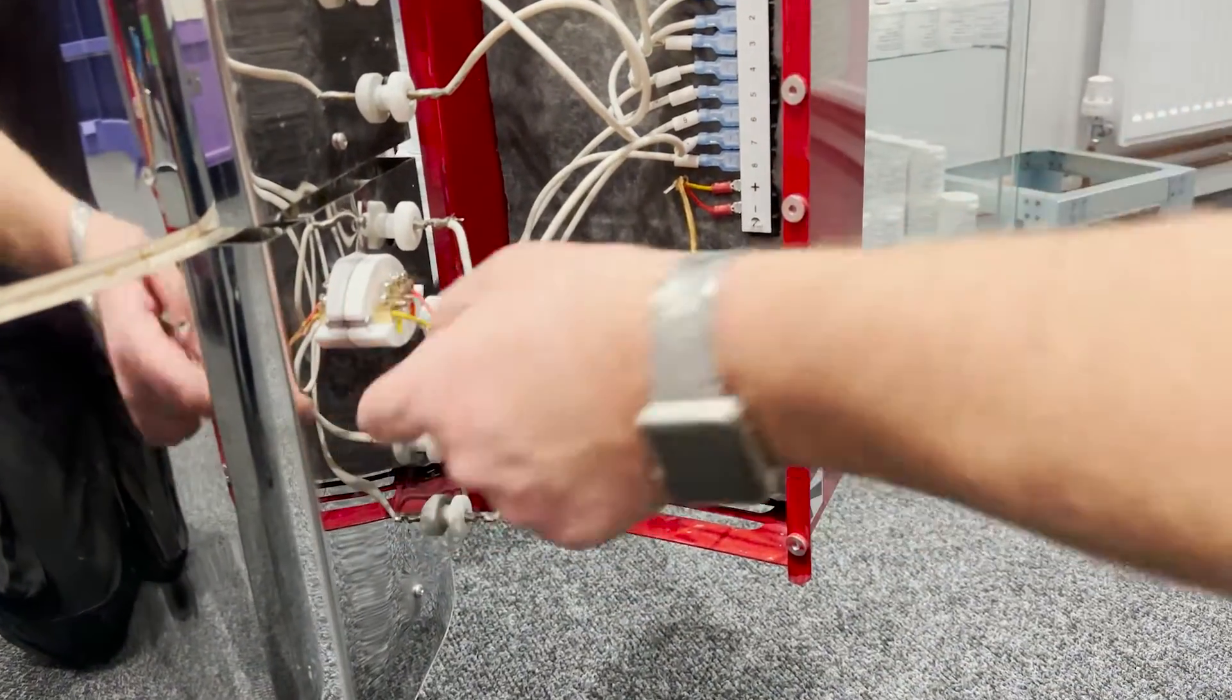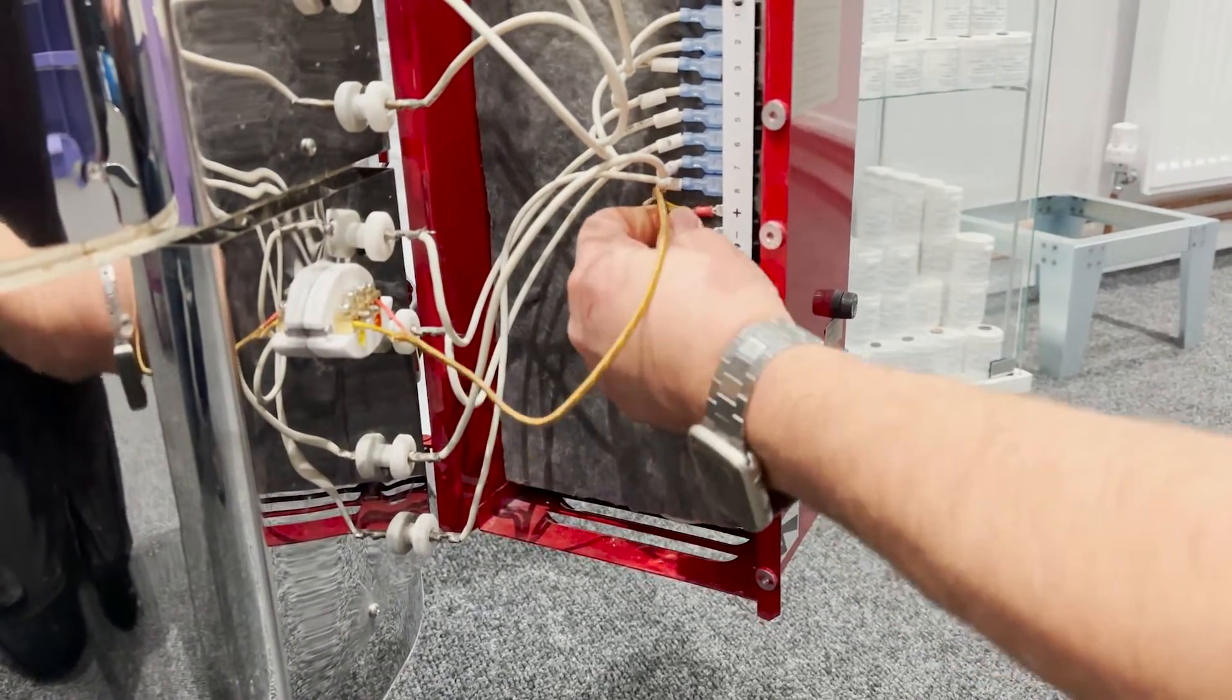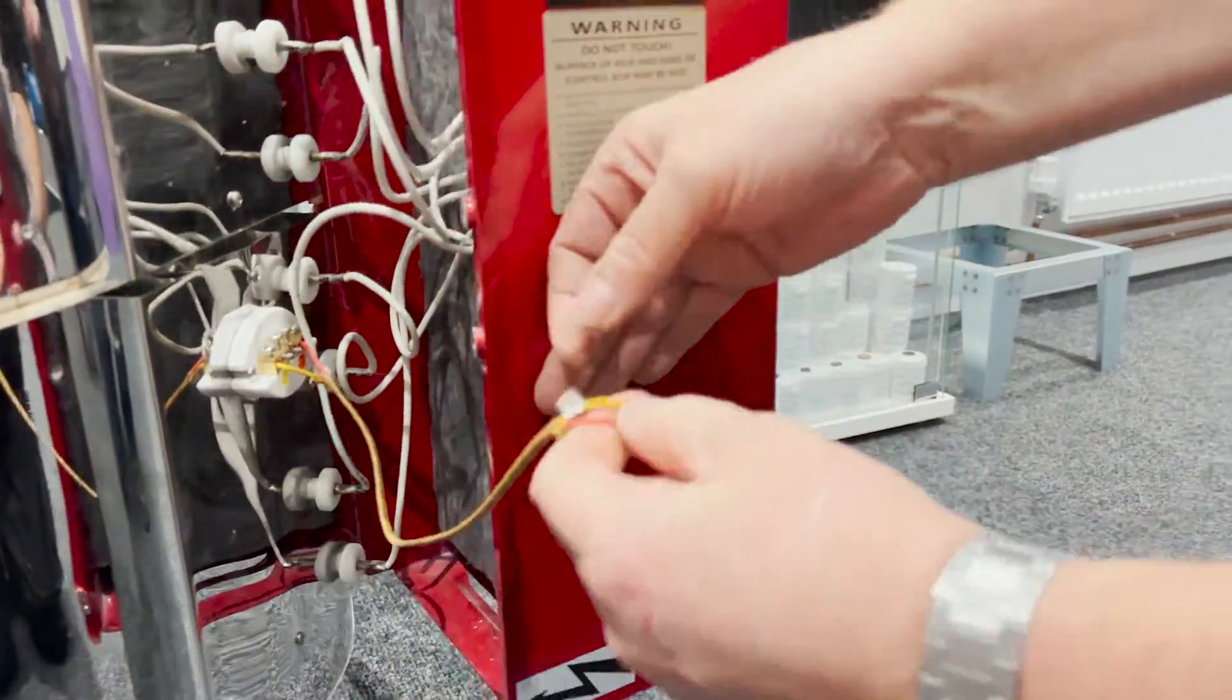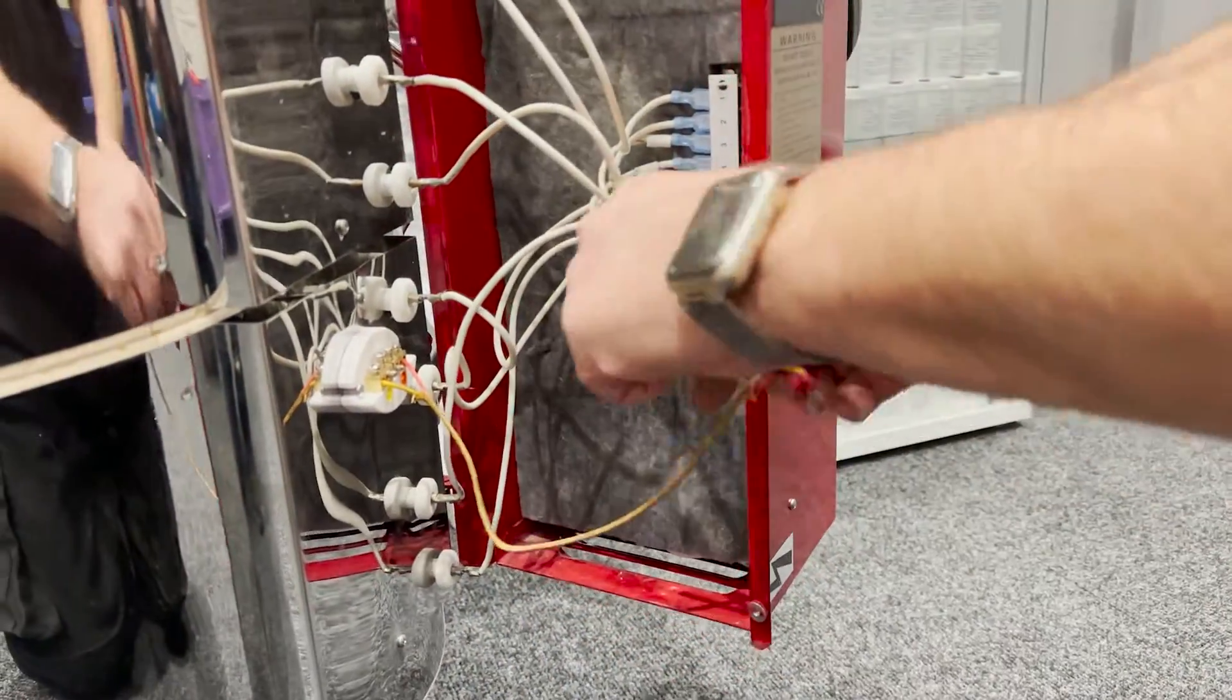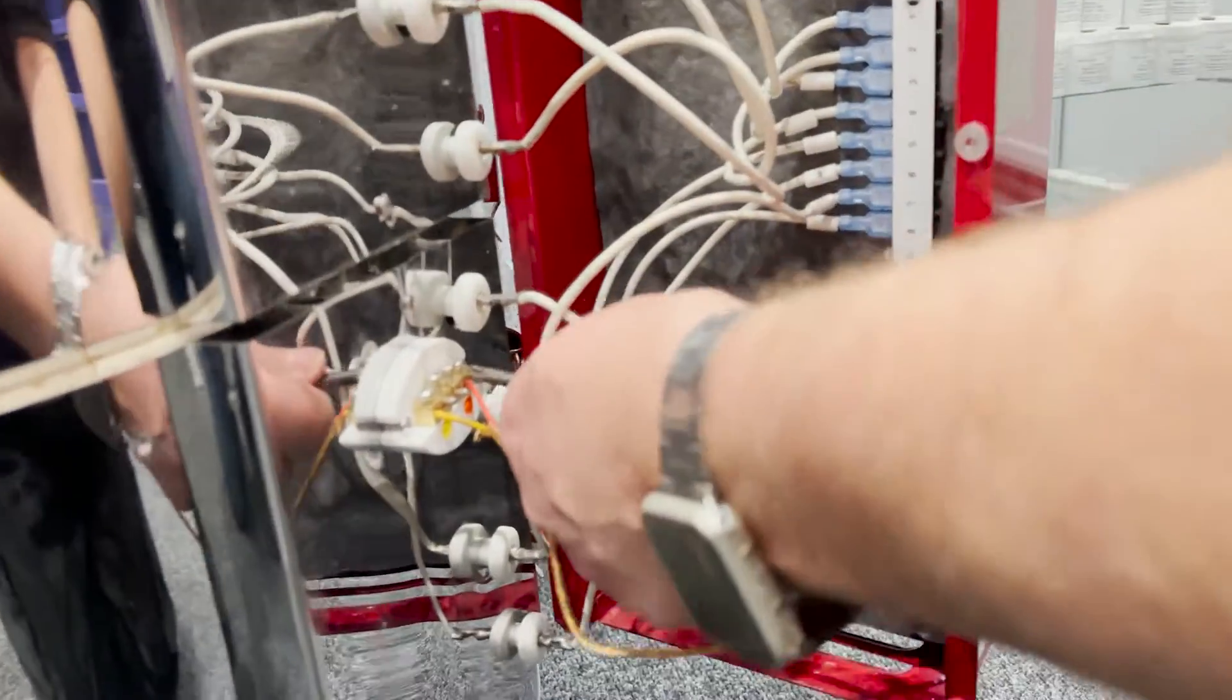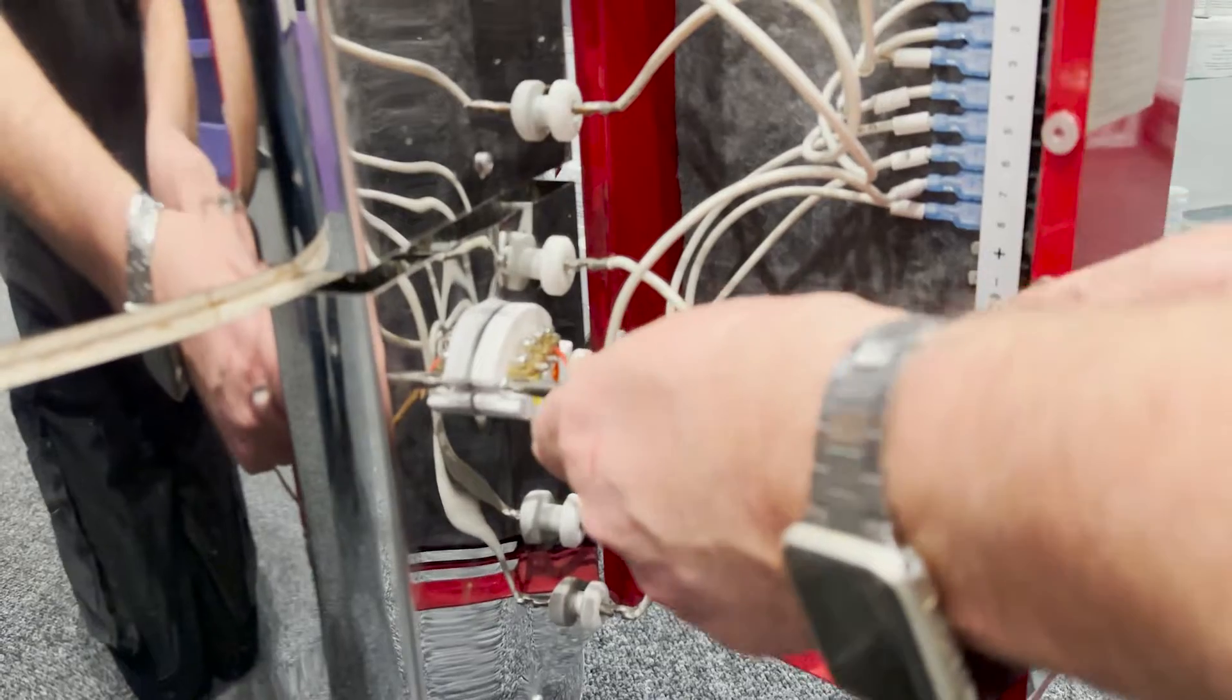Just pull the little spade connectors off the terminal block and then unscrew the two screws holding the thermocouple block in place. You should then be able to just pull the thermocouple out.